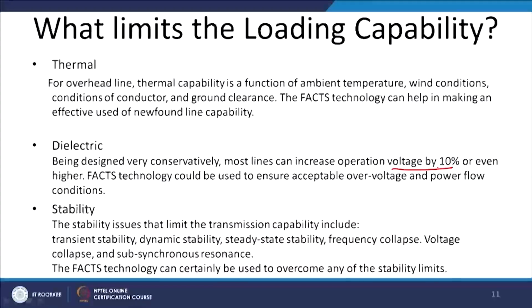In the same way, the dielectric limit comes with the voltage level, and it is also set for the worst environmental condition. For normal operating conditions, we can easily increase the voltage limit by 10%. Thus, FACTS enables us to smoothly carry 10% extra power without much change in the network. And stability is a very big issue in the power system. There are different kinds of stabilities.